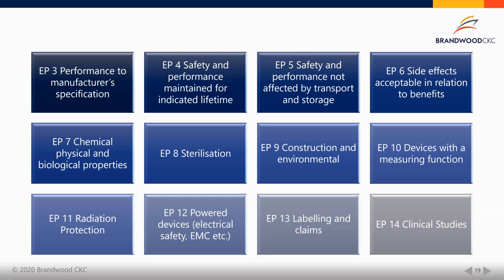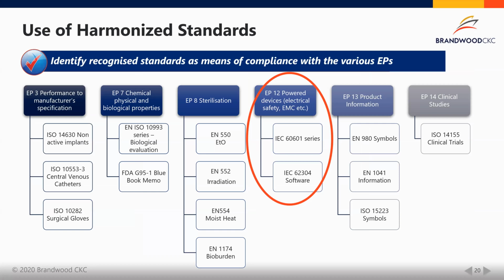So this is, like I said before, a really good way to show that you are complying with the EPs, through the use of harmonized standards. EP12 once again is circled here, and so I'm sure you're all familiar or will be familiar with 60601 and potentially 62304. These are standards that should be considered, I think, when you're in that design and development phase and you're looking at the regulatory side of things.